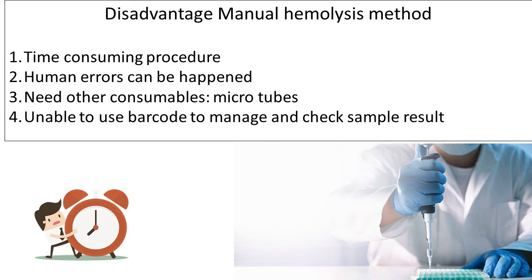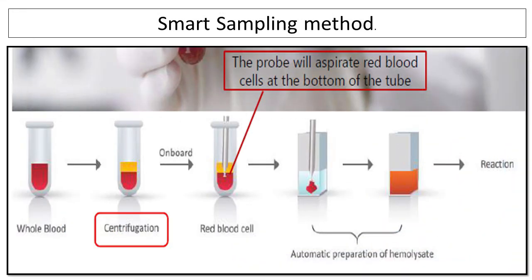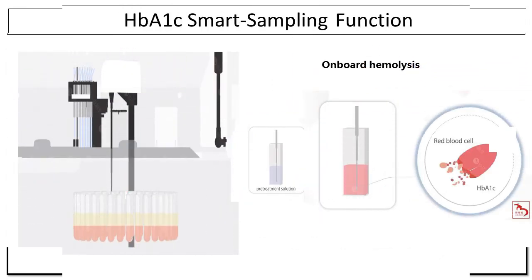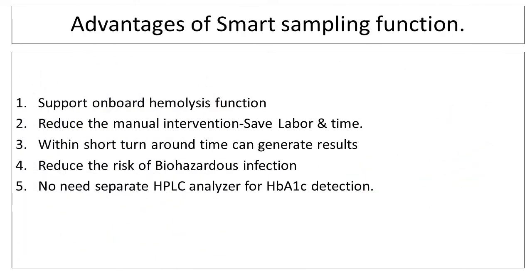In the smart sampling method, the probe will aspirate red blood cells at the bottom of the tube and automatically prepare the hemolysate — we call this on-board hemolysis. If your biochemistry instrument includes the smart sampling method, it supports on-board hemolysis function, reduces manual intervention, saves labor and time, generates results within a short turnaround time, reduces the risk of biohazardous infection, and eliminates the need for a separate HPLC analyzer for HbA1c detection.